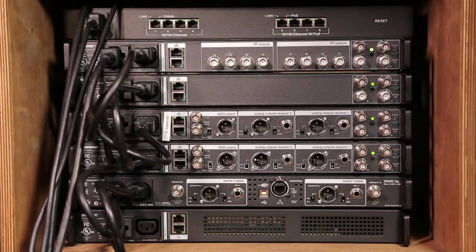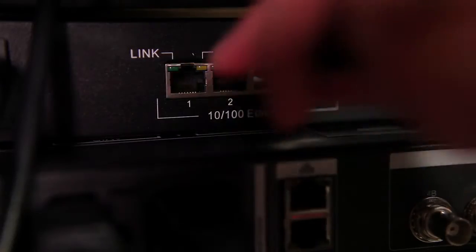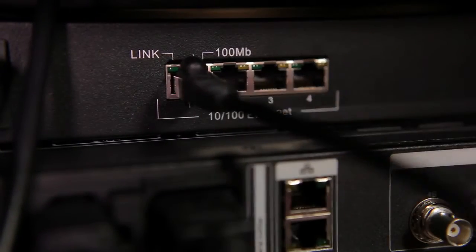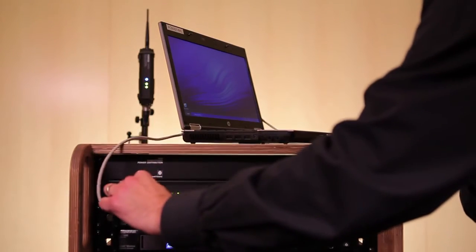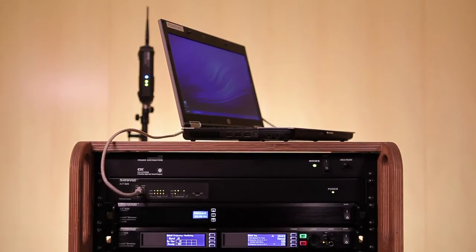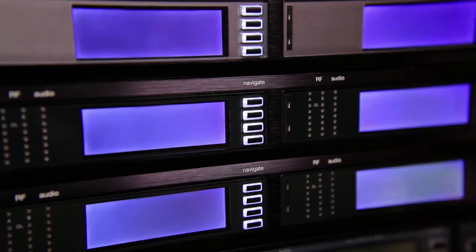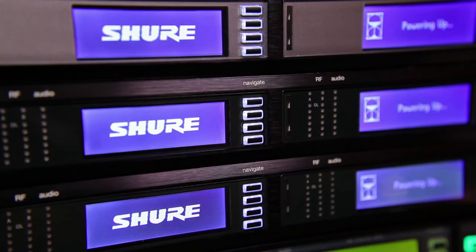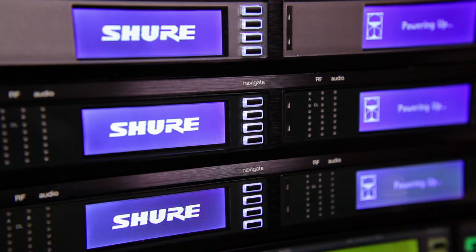Connect CAT5 network cables from each of your Axient components to the switch. Connect another network cable between the switch and your computer. Power up all of the Axient devices. The DHCP server will assign network addresses to all connected components.